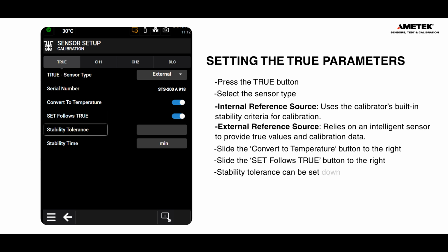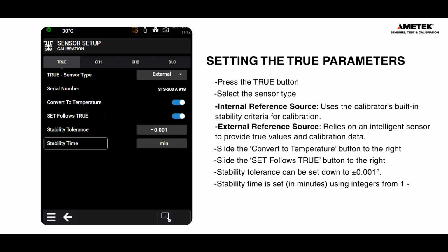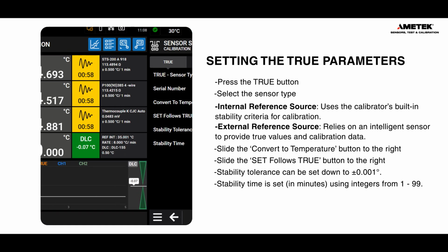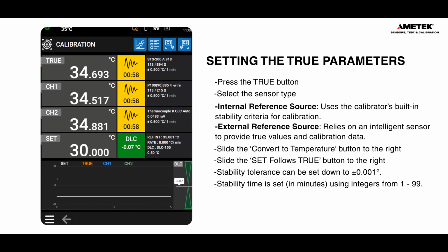You can set the stability tolerance as low as plus or minus 0.001 degrees. A lower tolerance takes advantage of the calibrator's excellent stability, but it will also increase the time needed to reach stability. Stability time can be set in whole minutes, from 1 to 99. When the true temperature stays within the specified stability tolerance for the set stability time, the stability indicator on the calibration screen will turn green.